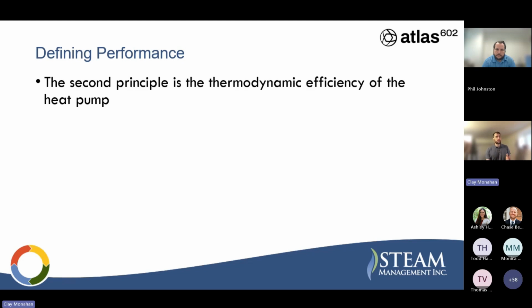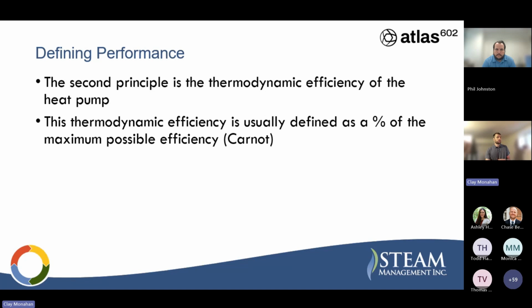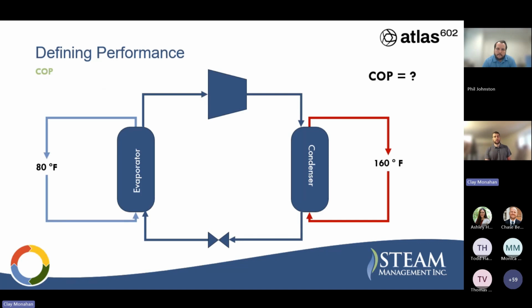The second principle is the thermodynamic efficiency of the heat pump. So that theoretical T hot divided by the temperature delta, we're never going to achieve that perfect thermodynamic condition because of losses in the system. So depending on the heat pump technology, we're going to achieve some percentage of that ideal COP. This thermodynamic efficiency is usually defined as the percentage of the maximum possible efficiency, or that Carnot efficiency. And that efficiency is the COP actual divided by the COP Carnot, which you can think of as just the maximum COP achievable.